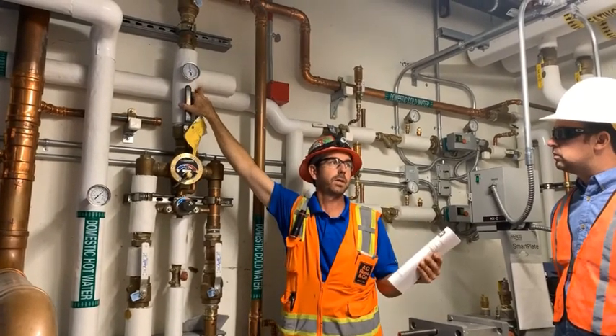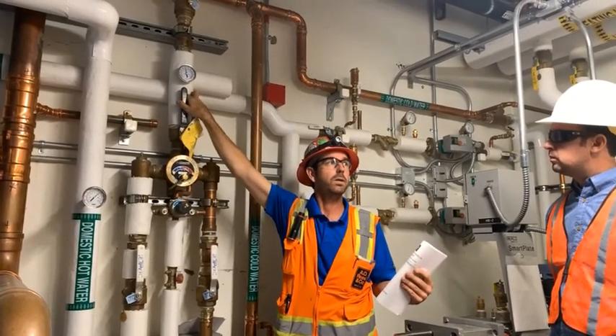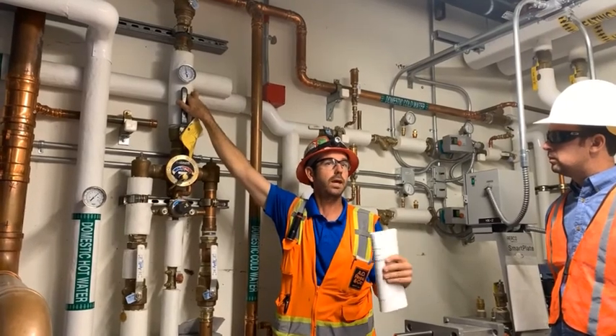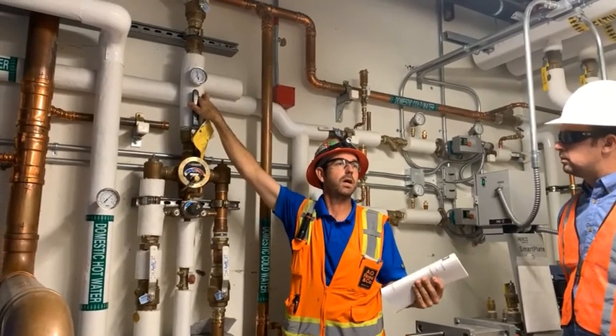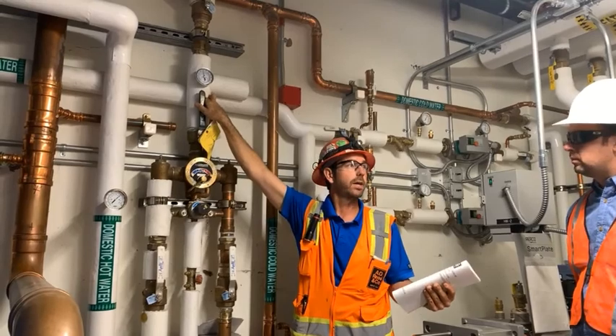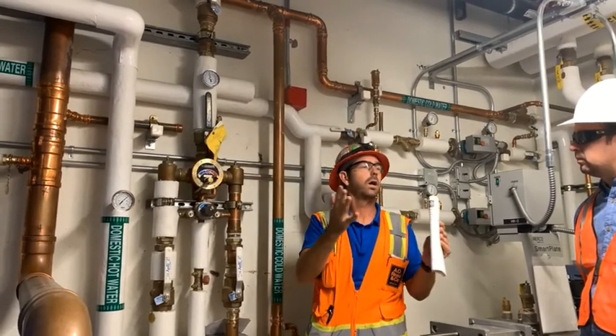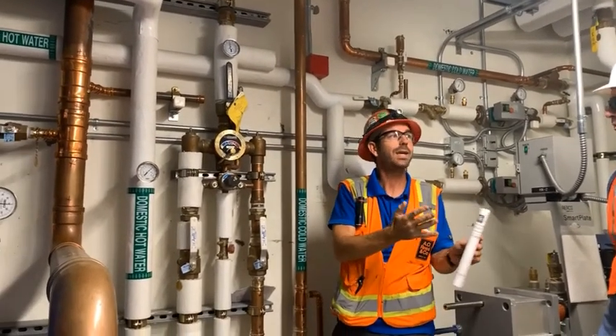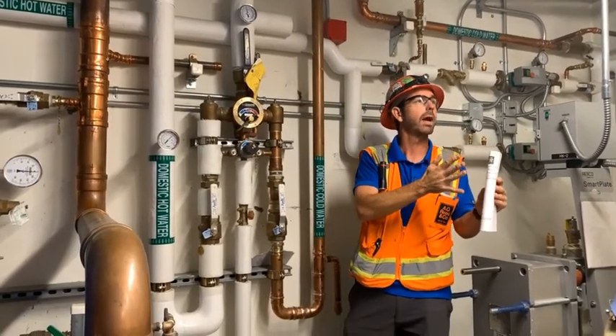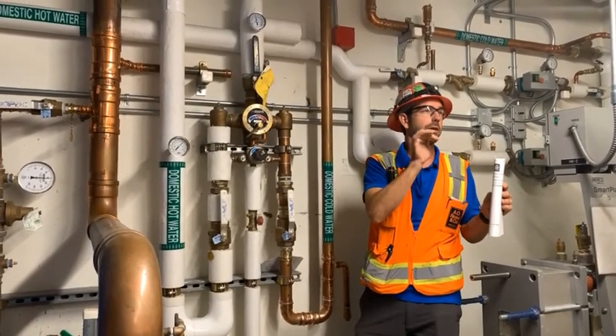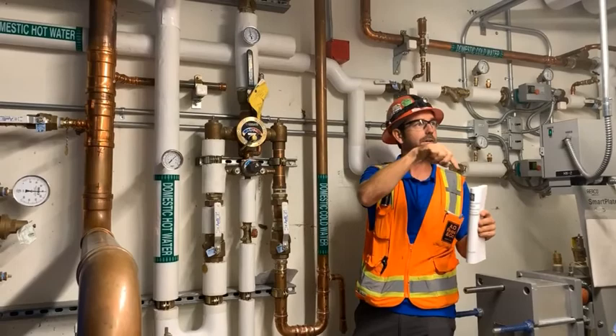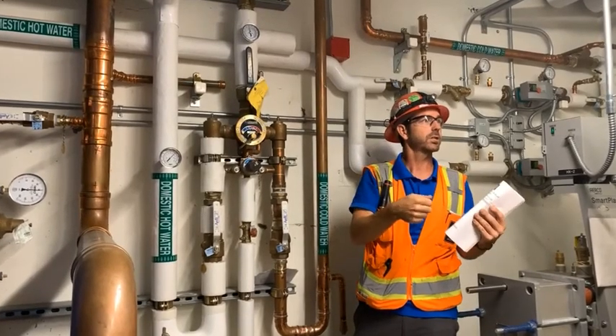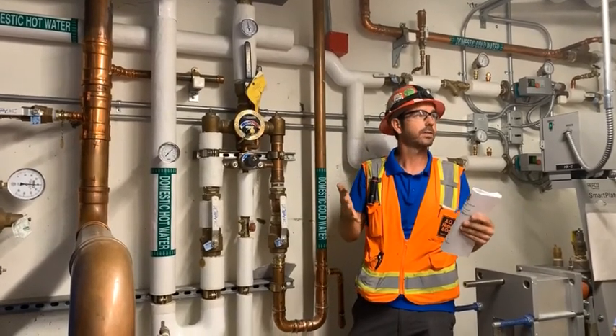Are you guys familiar with how domestic hot water return loops work? Okay, so normally the domestic hot water return loops are auto flows, okay? It automatically will flow a certain amount of GPM. Normally it's like 0.3, 0.33, somewhere around there. That way you always have water through that device, and then that way at the end of that fixture loop, when you turn on the fixture, you should have hot water within roughly 30 seconds, okay?